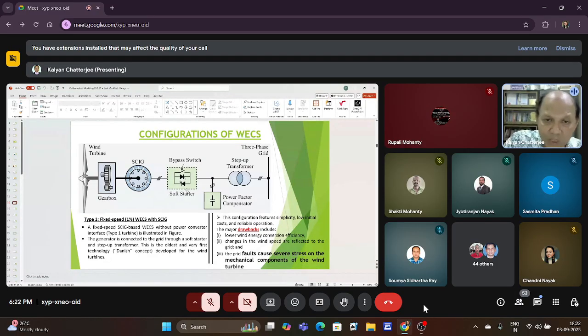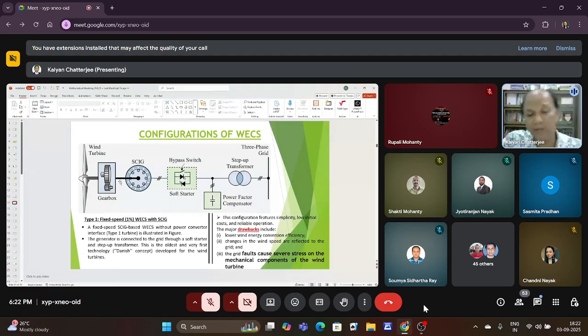Only a bypass switch is sufficient to control the system. The main drawback is low wind energy conversion efficiency, and changes in wind speed are reflected directly to the grid. Since this is a fixed speed wind turbine, if any fault occurs in the system, there is no fault ride-through capability. So any fault or disturbance in the grid causes the entire wind turbine to disconnect from the grid.